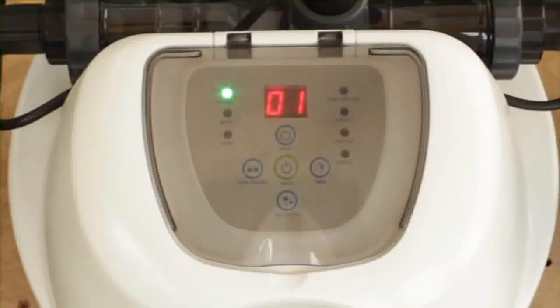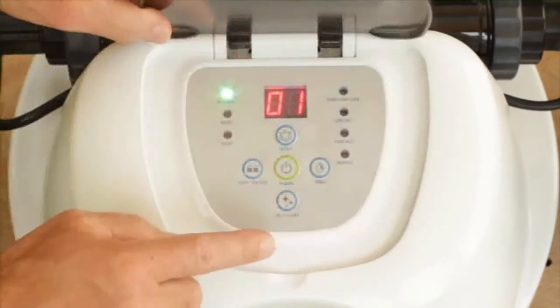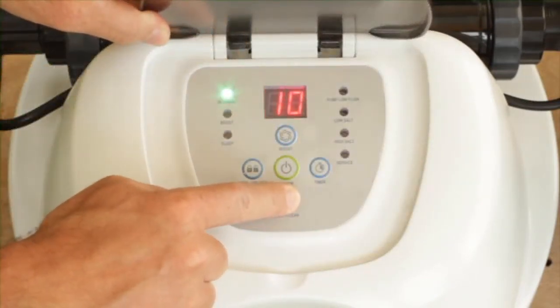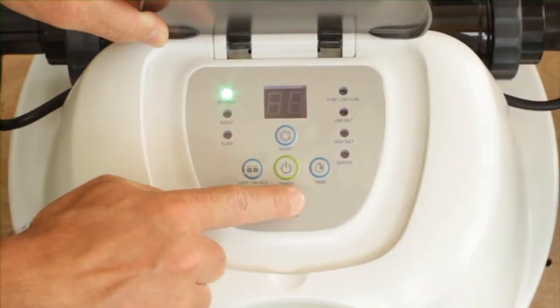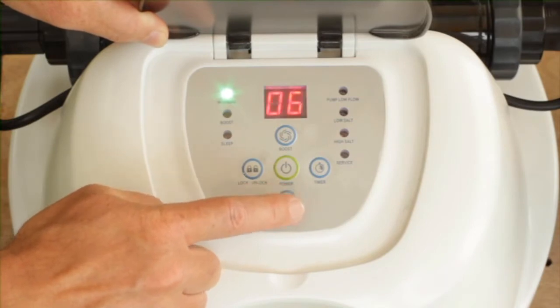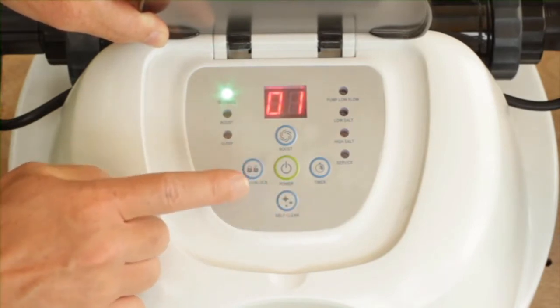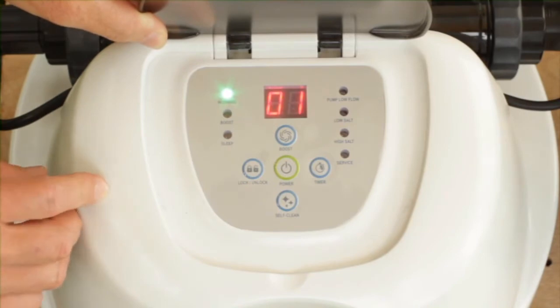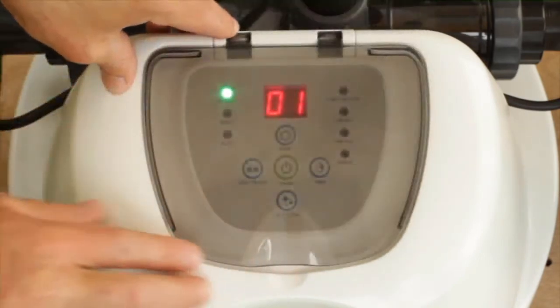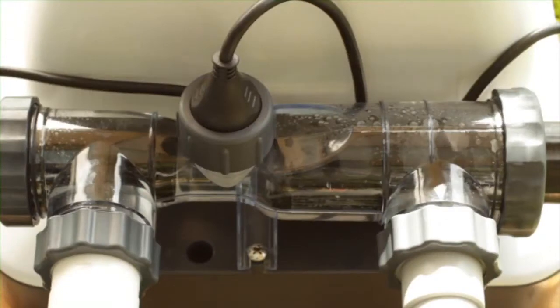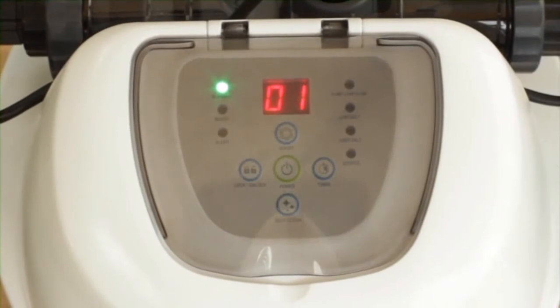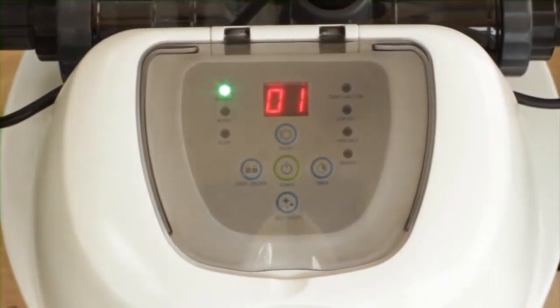Once you determine the recommended cycle time, press the self-clean button for 5 seconds until the LED display flashes with 10. Depending on your water calcium hardness level, press the button again for the desired times. There are only 3 cycle settings: 1 hour, 10 hours, and 6 hours. With the desired self-clean hours showing, press the lock-unlock button to lock the keypad controls and the LED display will return to the normal operating time. The system will reverse the polarity of the electrode every time according to the selected hours. Note: if you forget to lock the keypad controls, the system will automatically lock it and start working 5 seconds later.